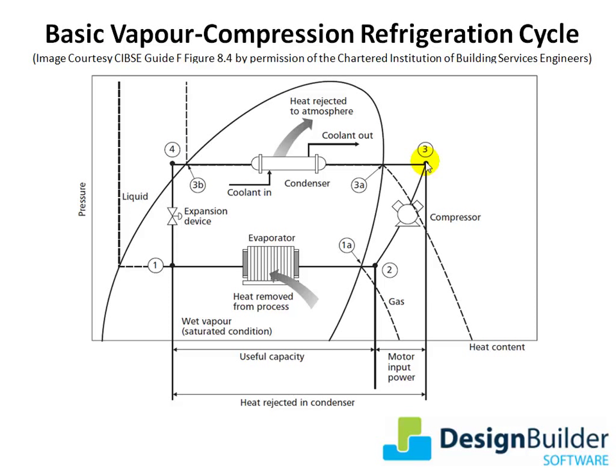The high temperature and pressure gas is then passed through a condenser between points three and four, where it rejects heat either to water or air in another heat exchanger. The cooling and enthalpy reduction results in the refrigerant returning to its liquid state at point four. The liquid is then passed through an expansion device, which reduces the pressure of the refrigerant and returns it to a low pressure liquid-gas mix, which can be used again to absorb heat from the evaporator.